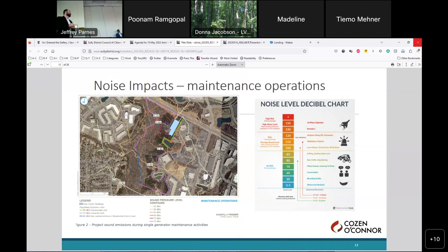When you say one at a time, how many are there? On a site like this, maybe 7 to 8. They run it bi-weekly and flip the schedule, so it's not 8 straight hours of running generators. You'd run the first week, then next the second, staggering them so they're testing different generators rather than running them straight for 8 hours.